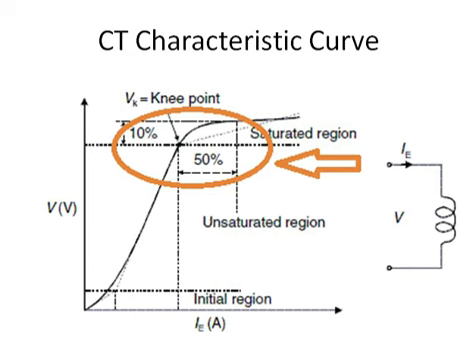This linear portion is the operational area of the CT. For a protection class CT — for example 5P20 — the '20' means up to 20 times its normal rated current the CT will work properly in this linear zone. The '5P' means the accuracy class is 5%. After this knee point, the CT will get saturated and will not work properly.